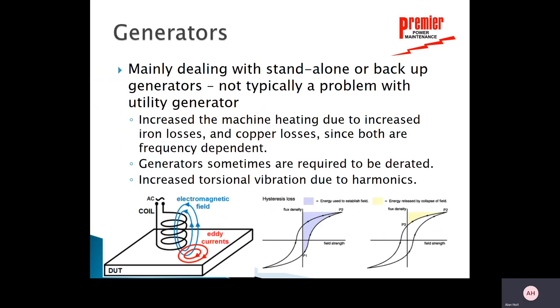When we start talking about generators — and this is also a transformer issue — we want to talk about hysteresis and eddy currents. This is not typically a problem with the utility generator but with backup and standalone generators. These harmonics can cause increased heating, and heat is always the number one enemy in electrical systems because it damages insulation. This heating has a lot to do with iron losses and copper losses.